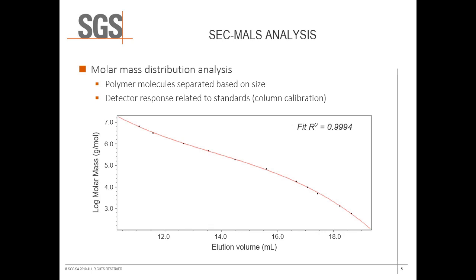This method may be adequate for a comparison between samples, but it is not a direct measure of molar mass. The results will be accurate only for the polymer used for calibration, and even the accuracy for said polymer is dependent on the accuracy of the molar mass value from the supplier's certificate of analysis. Additionally, the availability of column calibration standards is limited with regards to molar mass range and polymer type.